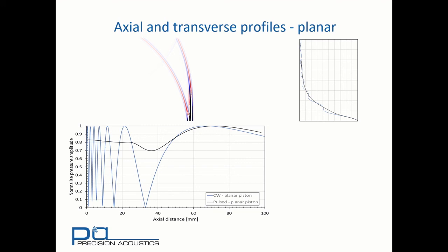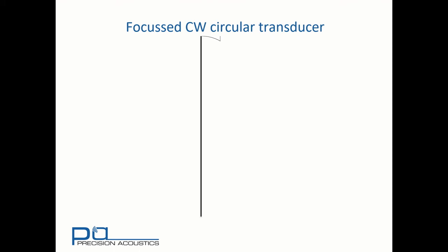With short signals, we get far less interaction. Now let's look at what happens with a focus transducer. The radius is the same as we've used previously, 10 mm, and we have a geometric focus of 20 mm. The centre frequency remains the same as well.